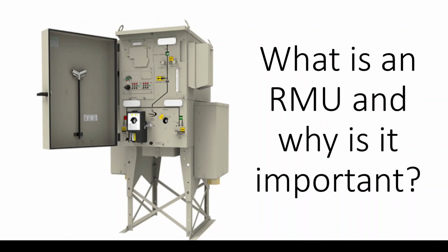So it is the point at which you tap from the available incoming medium voltage cables. So the RMU enables you to connect all the loads in a ring fashion. Therefore, when you are connecting all the projects or all the, let's say, the transformers and the equipment in a ring fashion, starting from the primary substation, you are providing power redundancy and therefore ensuring that the power is always available in case of failure in any part of the network.